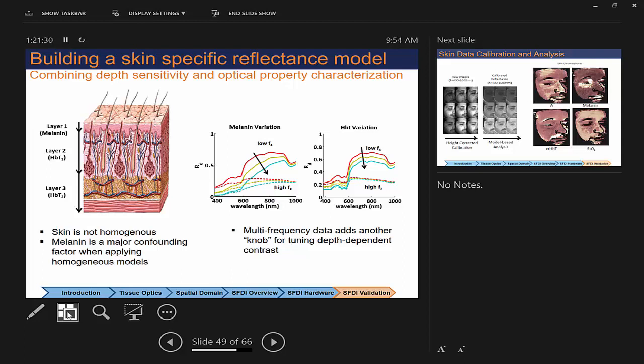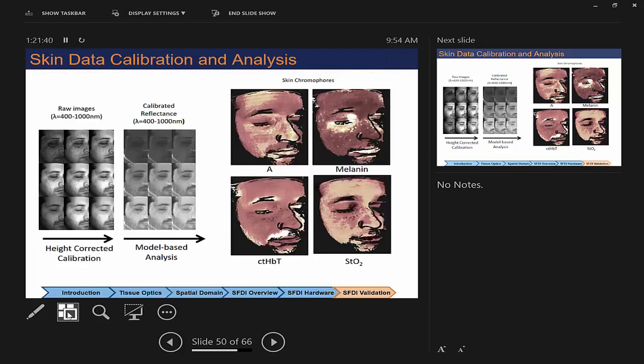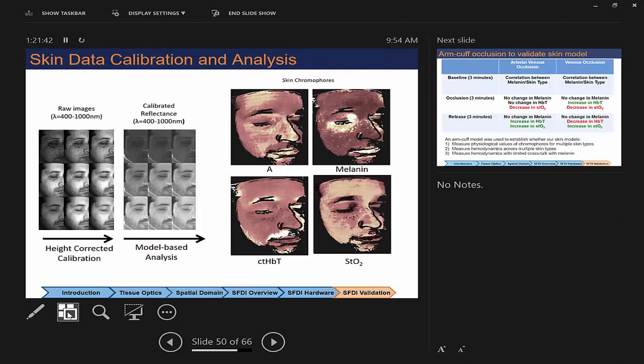And that's actually been really relevant. The superficial and the deeper hemoglobin have very different signals for diabetes, and the ratio between them is very diagnostic for risk of ulceration. So in our real data system, we have multiple wavelengths and spatial frequencies. These are the raw images, then we calibrate it, and then we put it through a wavelength and spatial frequency dependent model to calculate chromophore maps.